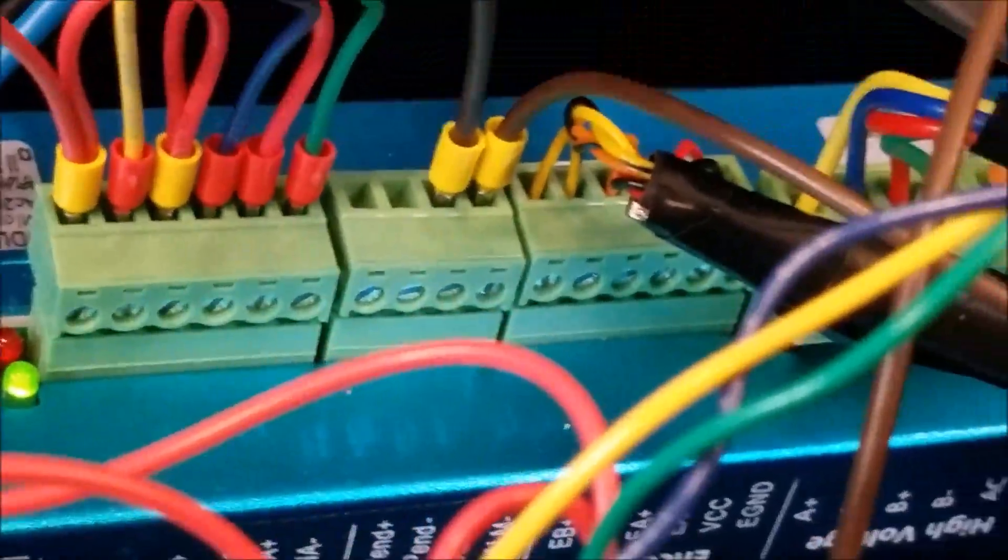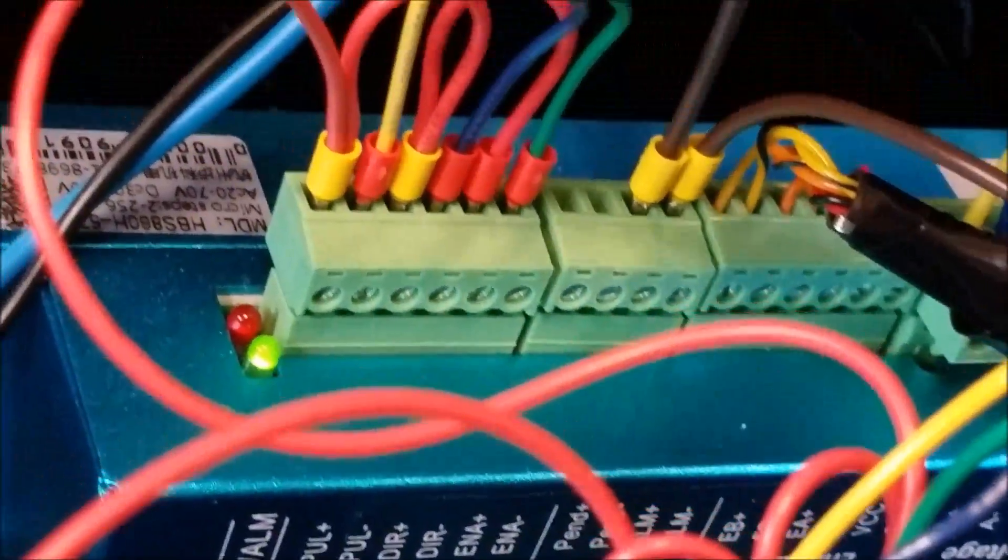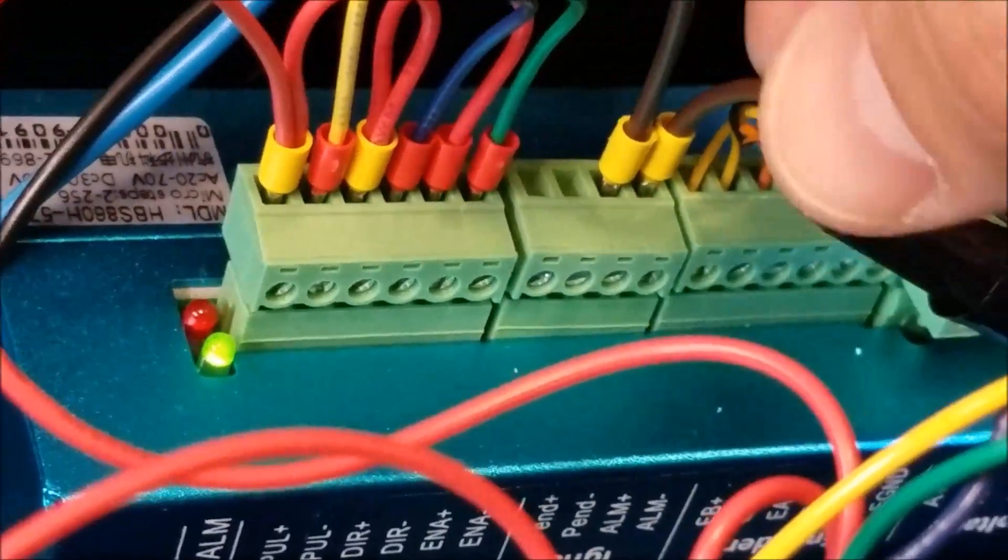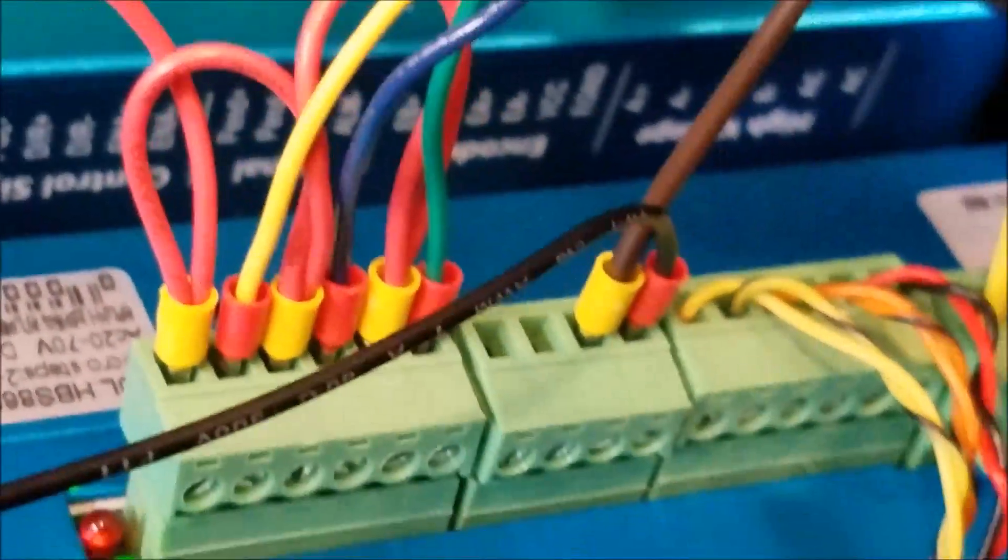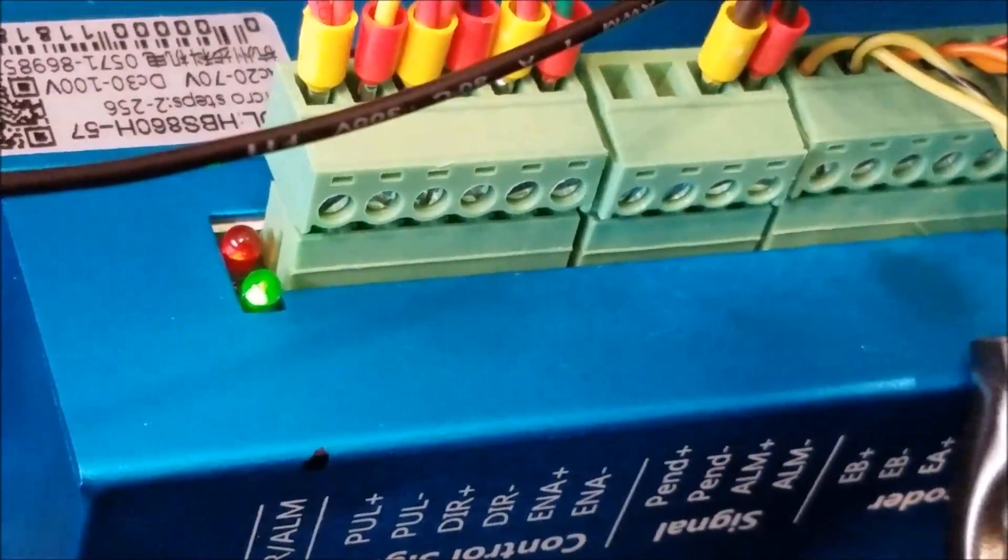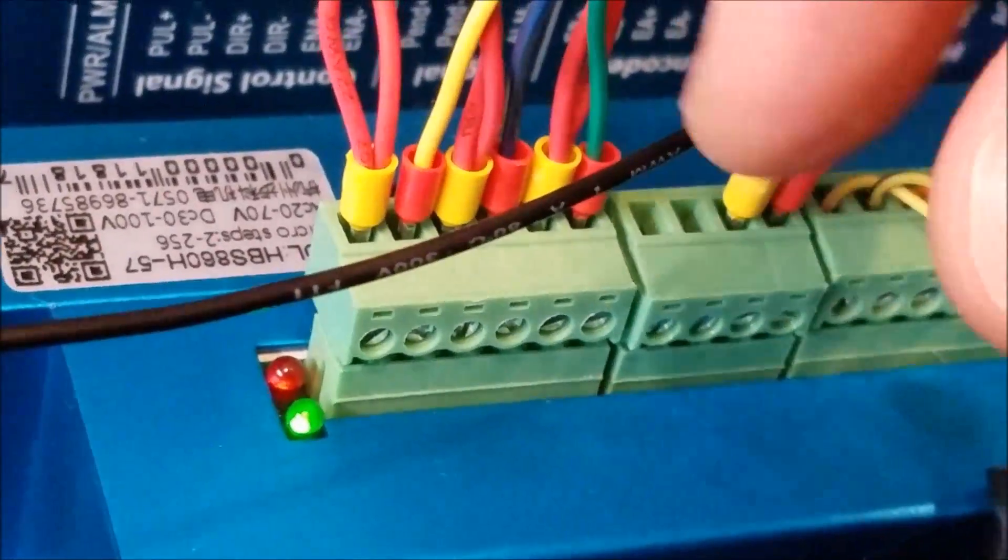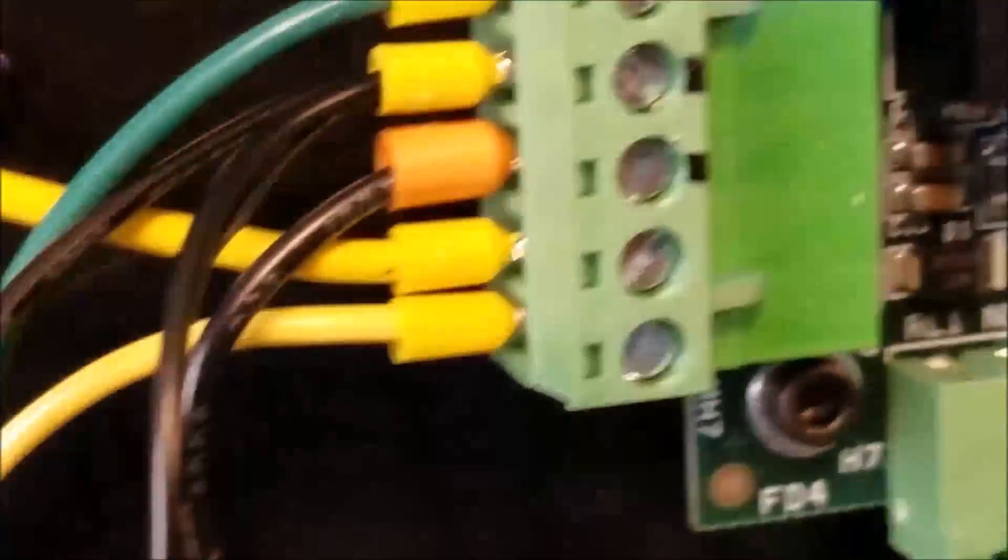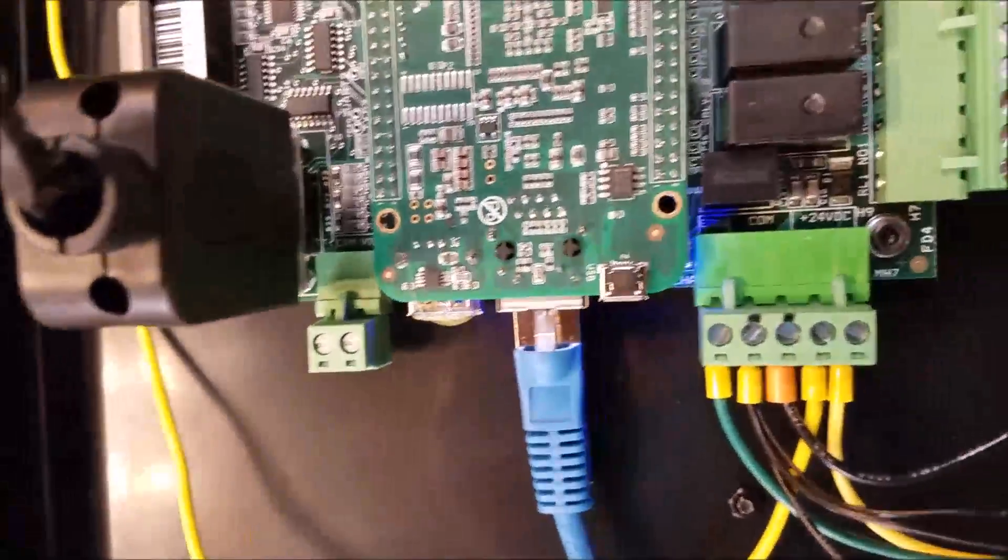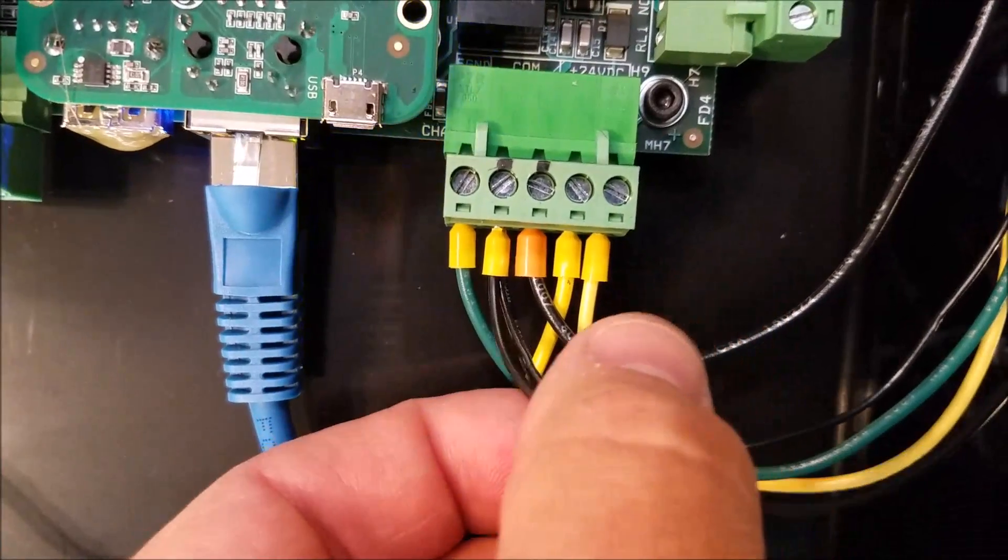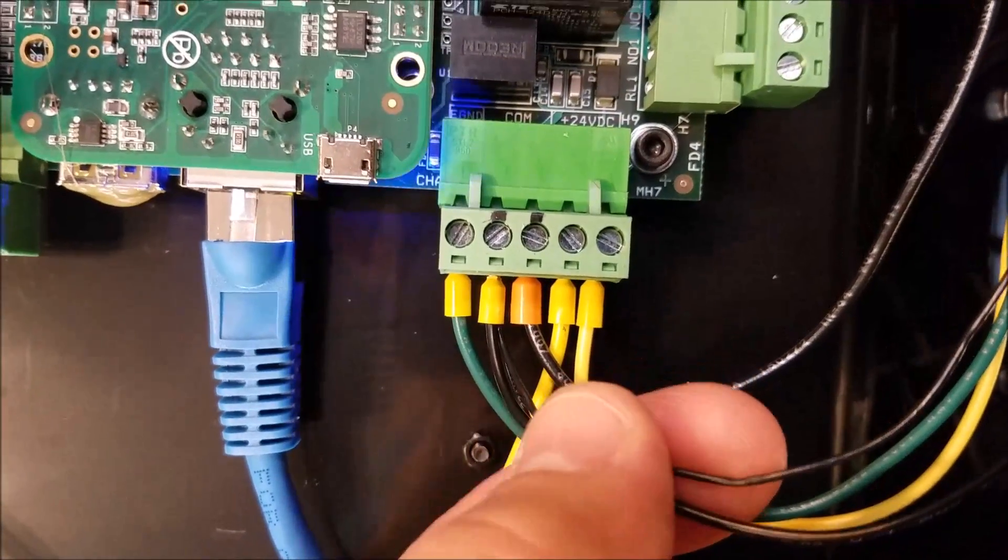What we have here is the brown wire coming in to the alarm positive. Then we have another brown wire coming out, jumping over to the second drive, going to the alarm positive. And then we have a negative wire—a black wire—going all the way back up here to our same old common, just like it's called out. You'll notice I have several wires now coming into this one common.